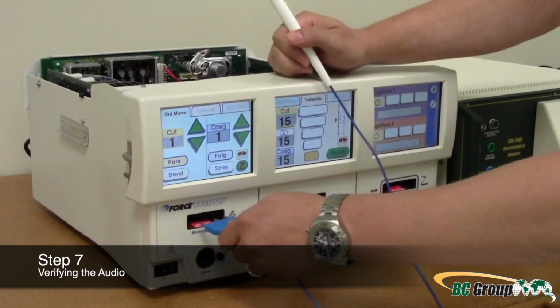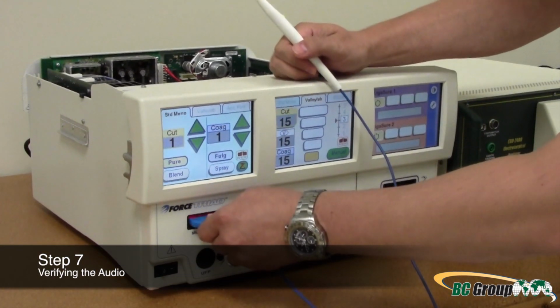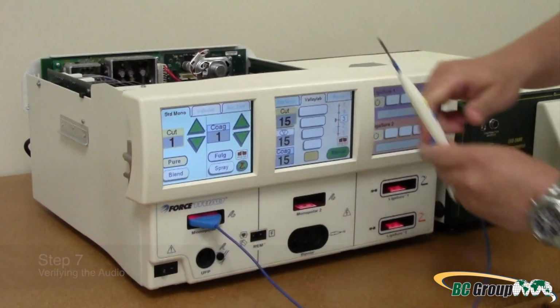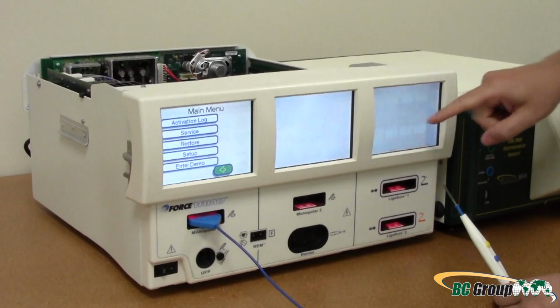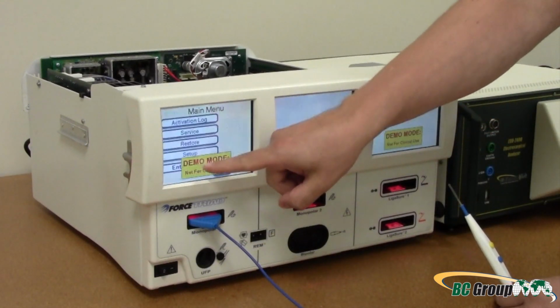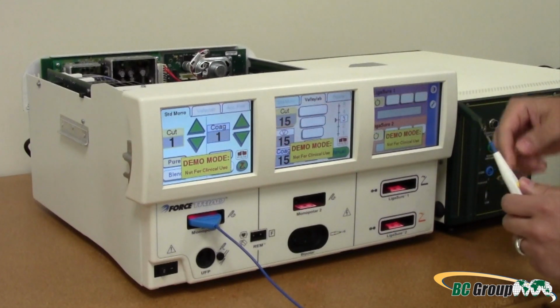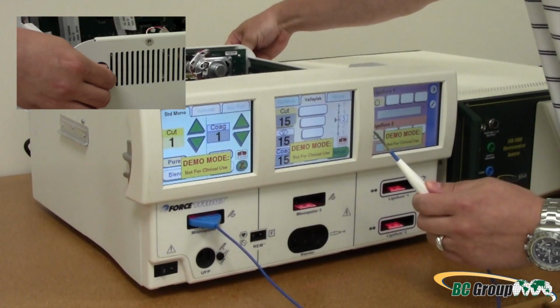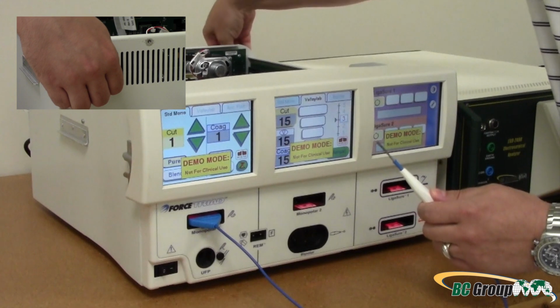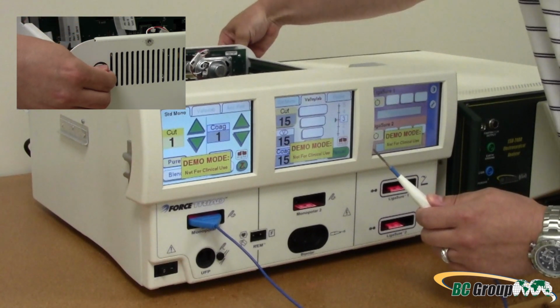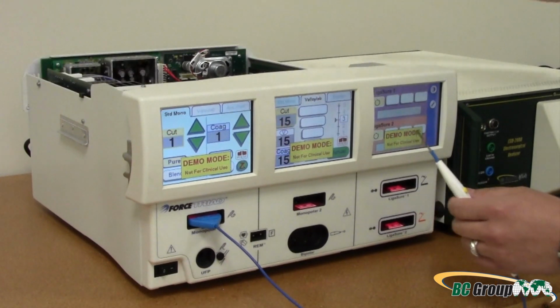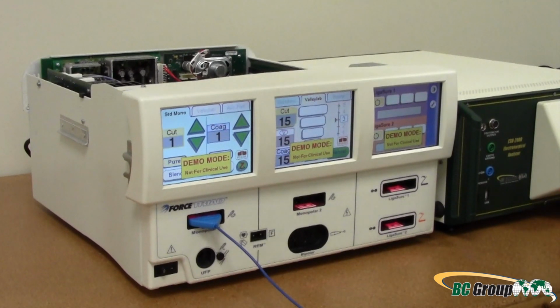Step 7. Verifying the audio. Connect a hand switch to the monopolar 1 port on the generator. Enter Demo Mode. Activate the cut output from the hand switch. Rotate the audio knob on the rear of the generator from high to low volume. Verify that the audio is active and distortion-free.